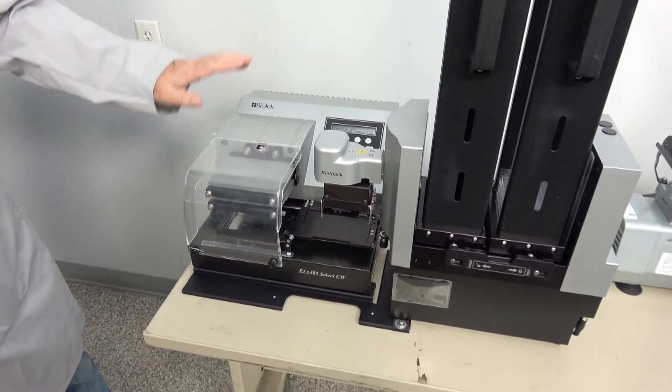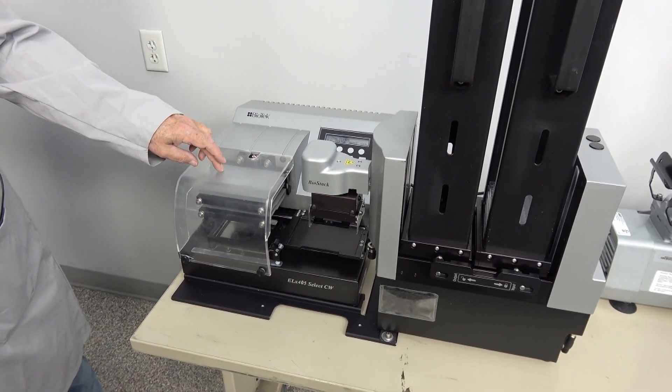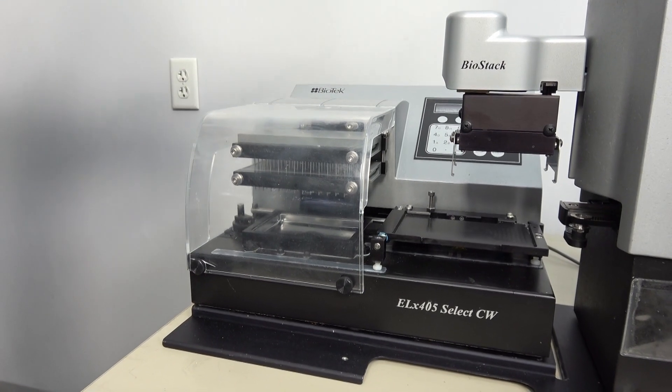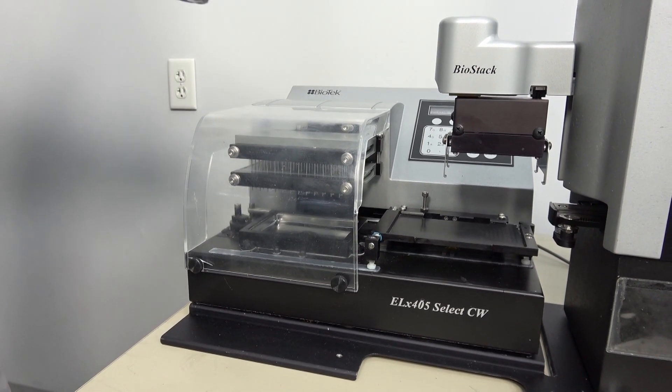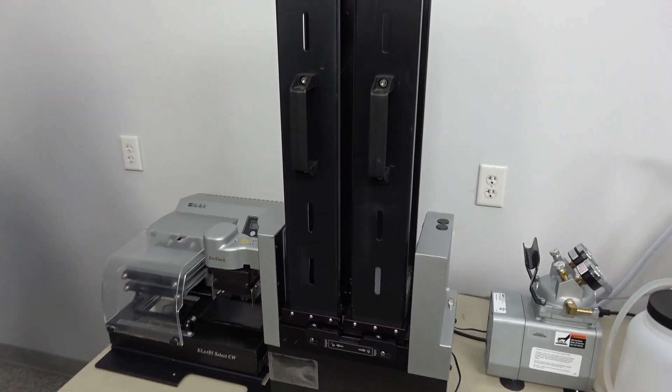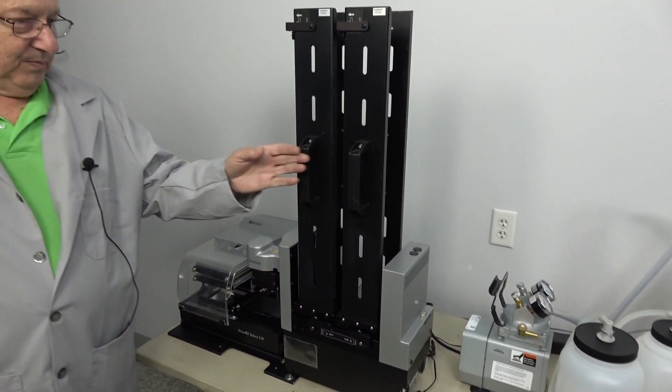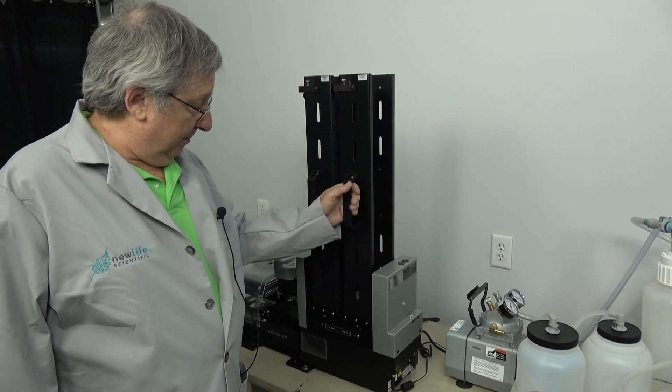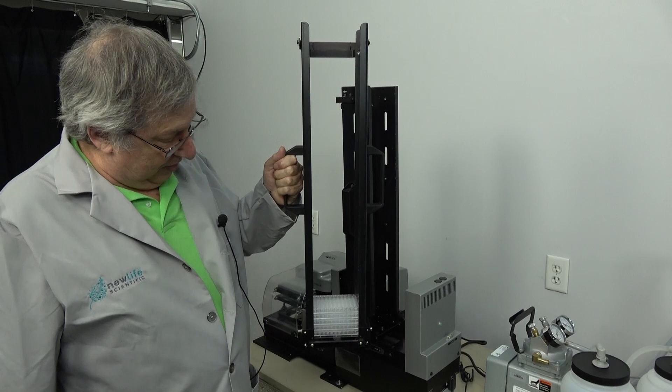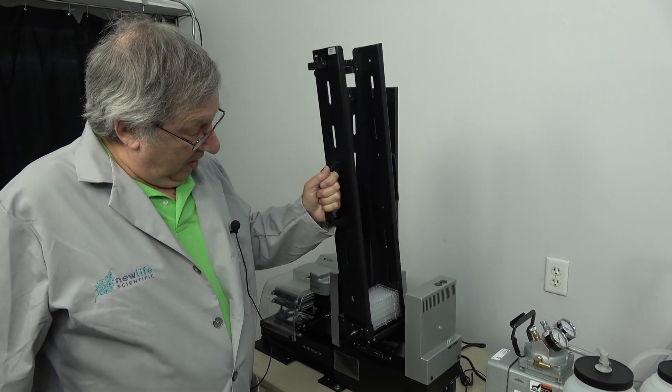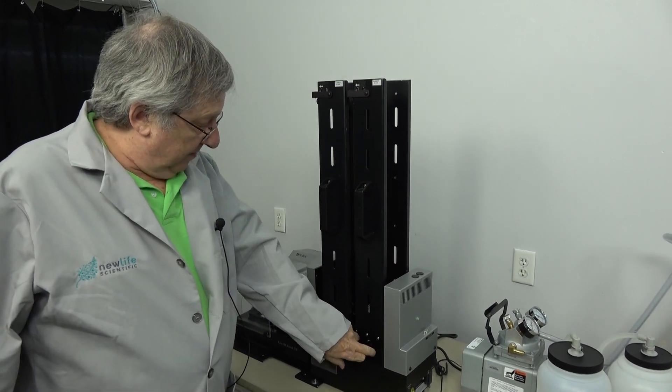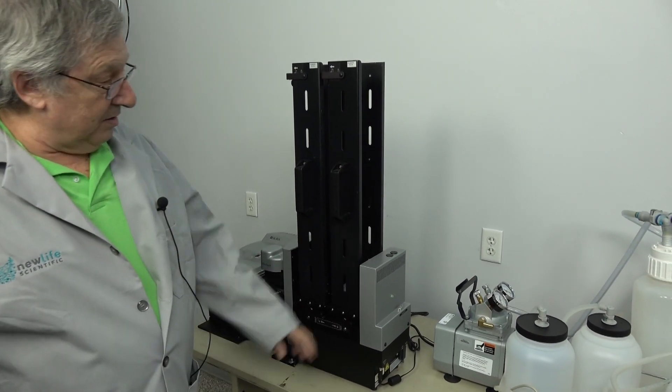This particular unit is equipped with a 96-well head plate washer. As I mentioned, it has the BioStack with the tall stacks, which can hold lots of plates. We've got five of them in there, and we're not even close to the top. So you can run all night. It locks into place.